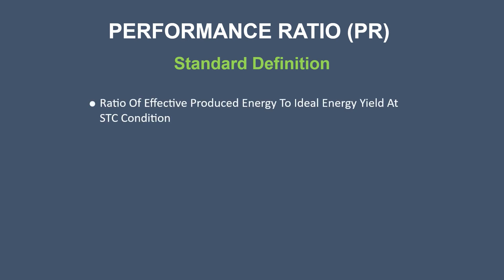So what is performance ratio, or PR, for solar PV power systems? PR is the ratio of effective produced energy to ideal energy yield at STC condition. As it is a ratio, it is unitless, and globally it is denoted as a percentage value.